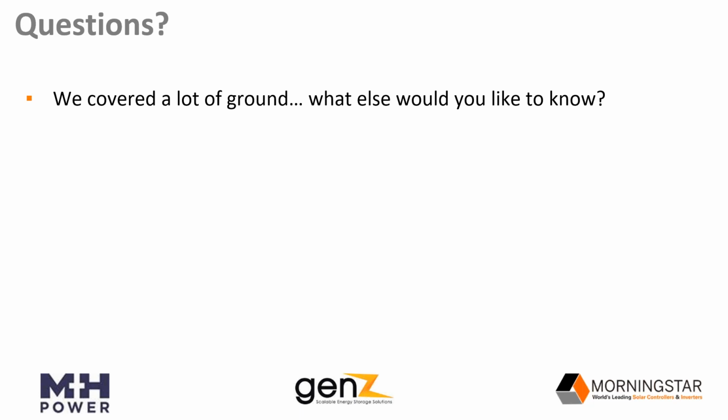What I would say, even though we have some specific manufacturer configuration files, as I talked about, one of the more generalized settings or suggestions I would make when you are supporting lithium with our products is primarily to disable the temperature compensation, so that it's giving a consistent regulated output, since the BMS takes care of a lot of that, and lithium's not nearly prone to the temperature range swings that lead acid deals with. And the other is to pay particular attention to the float setting, because some lithium batteries may have a very minor float setting, some do not really actually want it at all. So you would want to look at purely an absorption level and make sure that that's fixed. If you disable those two settings, the TriStar PWM can do well, but even though the gel setting is the most conservative, I would take it a little bit further and try to customize that on the TriStar PWM if possible.